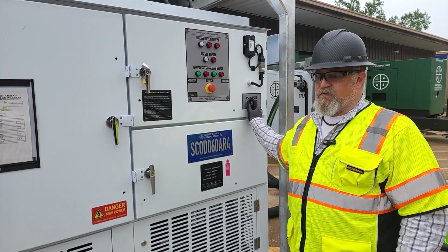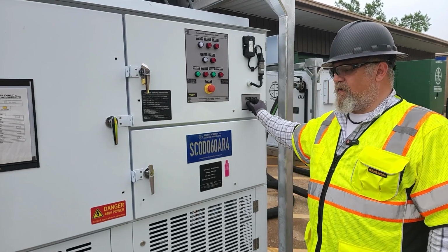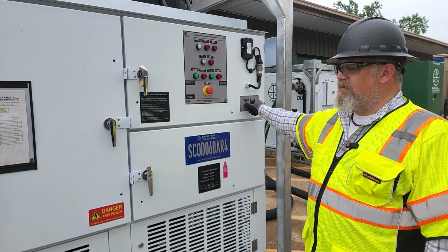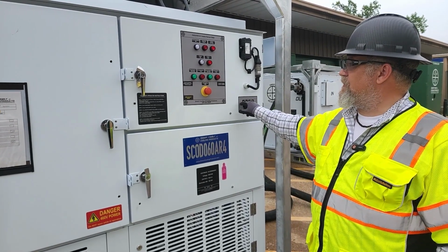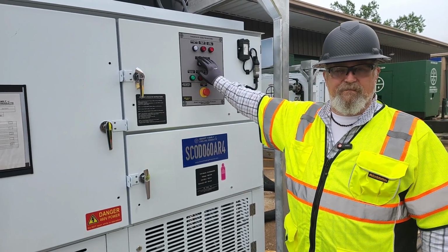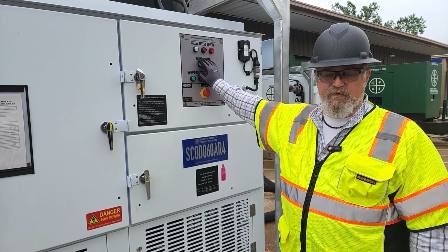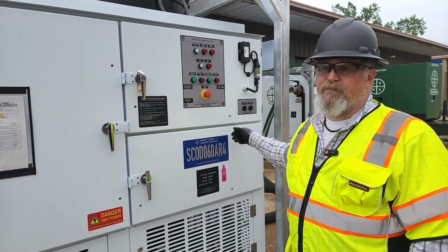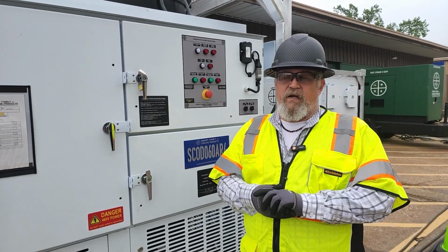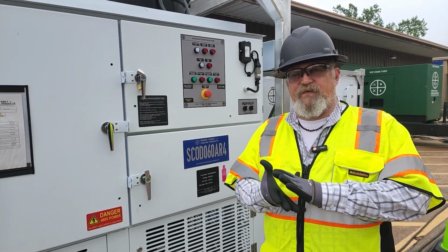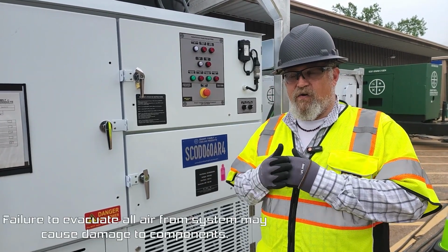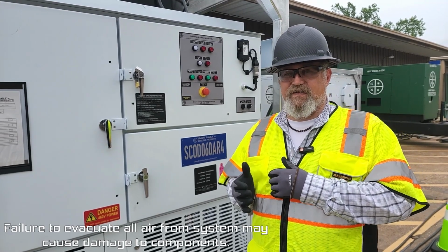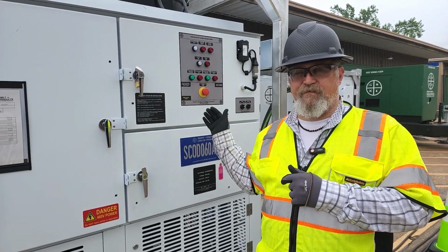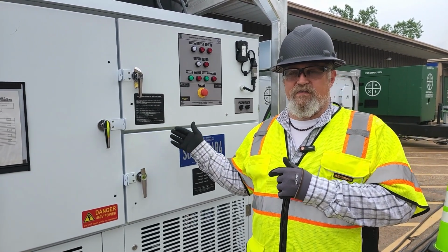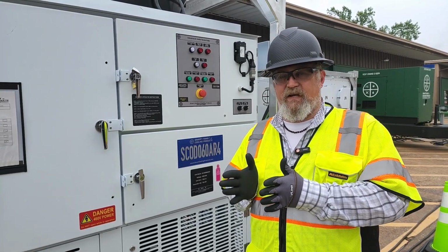So to remove the trapped air pockets, all I want to do is turn on my pump for several seconds. So I'm going to turn the pump on, and I'm going to watch for my pump to come on. And then I'm going to turn my pump off. You may need to do this several times in order to get all of the trapped air pockets out of your system. Okay, now remember, leave your filler hose on to fill in those gaps where that air has vacated the system.